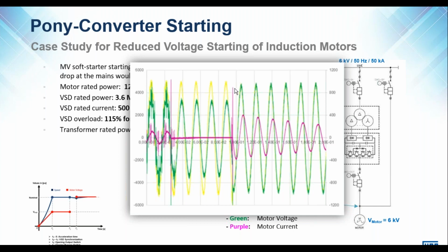However, the current peak or the current spike during that transition is not more than about 1.5 times, in this case, of motor nominal current. So still a lot lower than a direct online situation. And then after some time running online, that current settles down to full load current value, and then the full load can be applied to the machine.